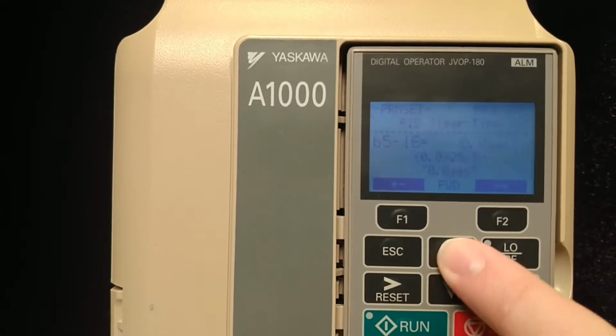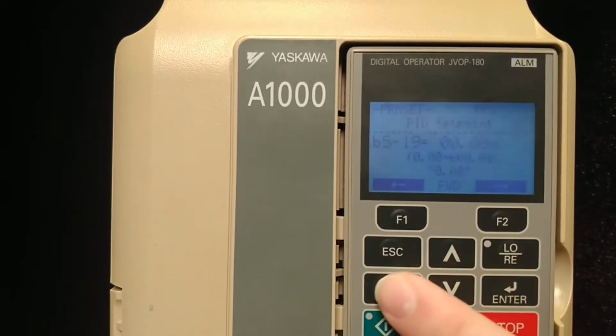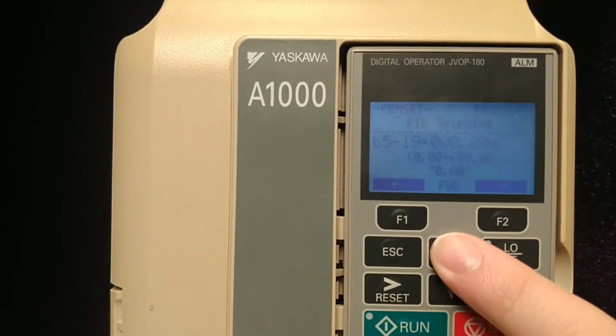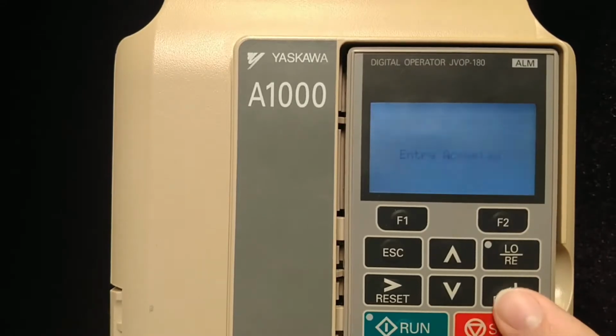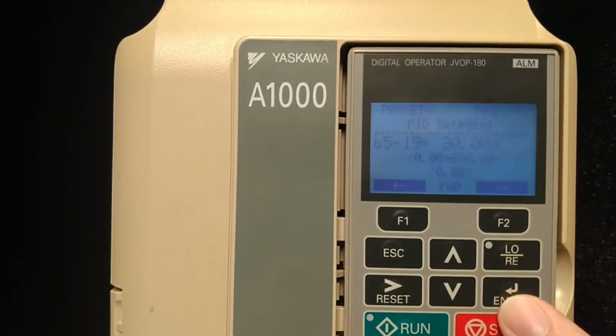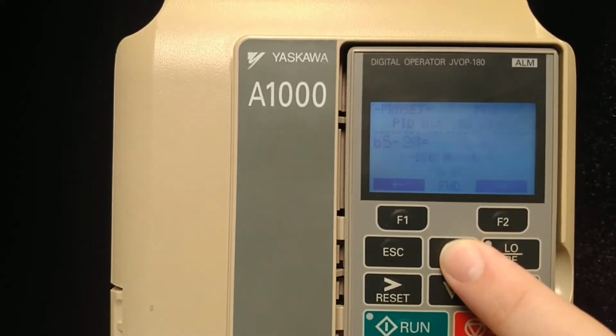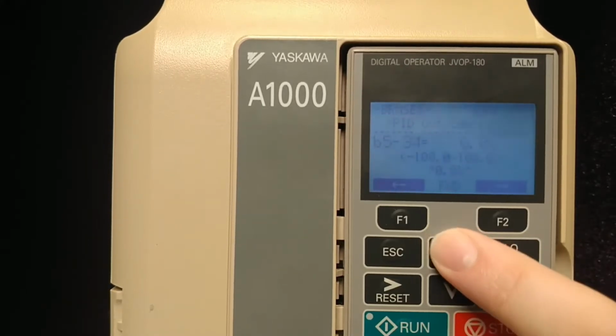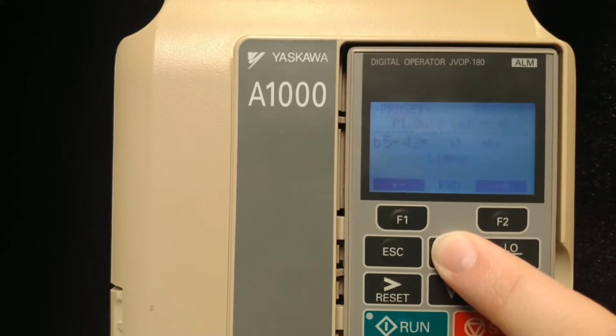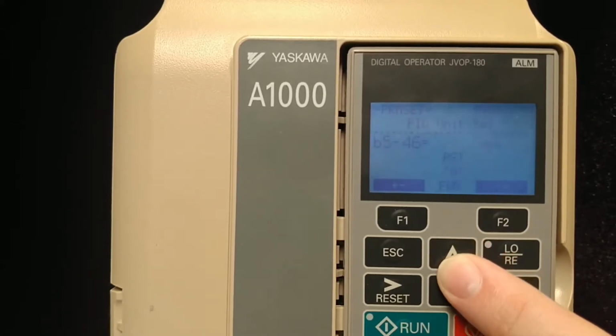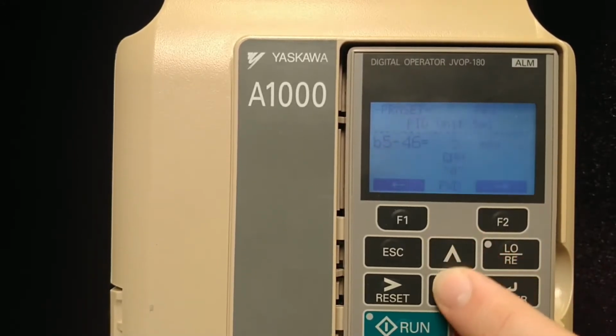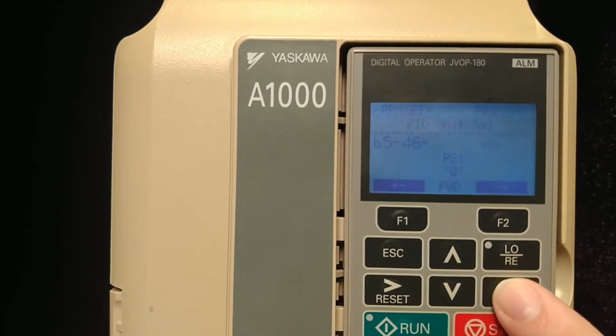The next parameter to set will be B519. This will be the actual set point that you want the drive to reach. As of now, this reads 30.00 WC for water column. This is for the default. If we want to change what PID scaling is set in, we would go to parameter B546. With B546, we can choose between water column, PSI, gallons per minute, degrees Fahrenheit, etc. Most often it's used for PSI.